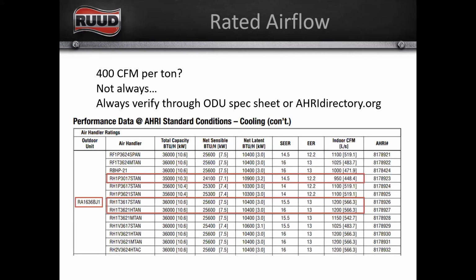So if we just assume that we're supposed to be moving 1200 CFM through this indoor coil, and we configure it that way without checking to see what the rated airflow actually is, we're going to be pushing way too much air through this coil. And our charging chart is not going to be right. You're never going to get the latent capacity, meaning you're never going to be able to get it to dehumidify like it should. It's not going to run the way that it should. It's not going to be as efficient as it should. You're going to have a lot of problems. So you've got to know what your rated indoor airflow is for any matchup, and then you can adjust your airflow accordingly. Any questions about that before we move to calculating capacity?